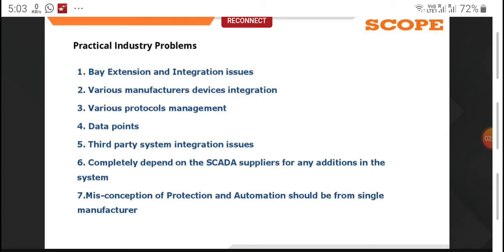The second is integration of devices from various manufacturers. That is also a very critical issue. If I have one OEM and another OEM, say 2-3 OEMs, even though they support the 61850 protocol, for the integration of all these relays to the SCADA you again have to depend on the different OEMs. The OEM has to create an ICD file, SCL files, and give them to you. Then the other OEM does the same configuration in the relay and gives it to you. Then you take all this data, configure it in the SCADA database and try to connect it.